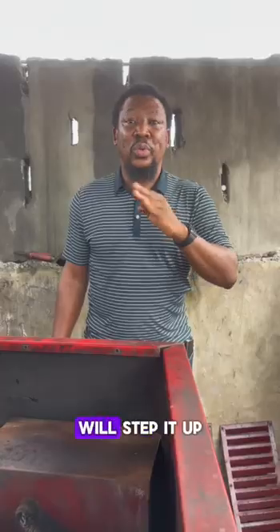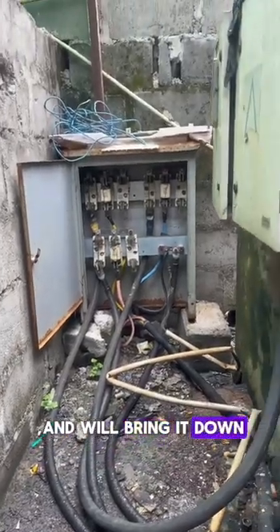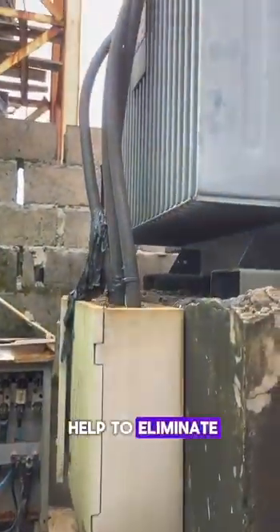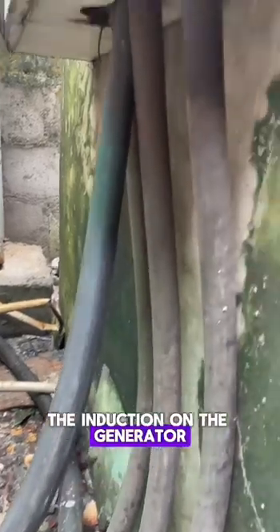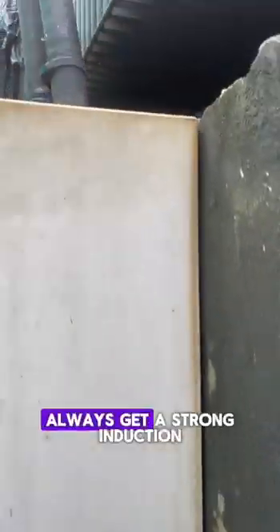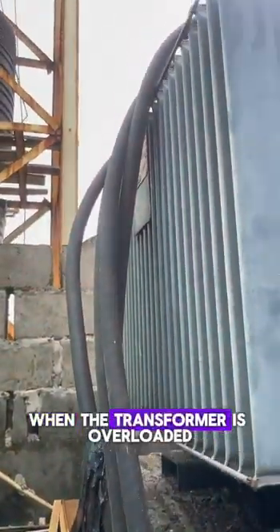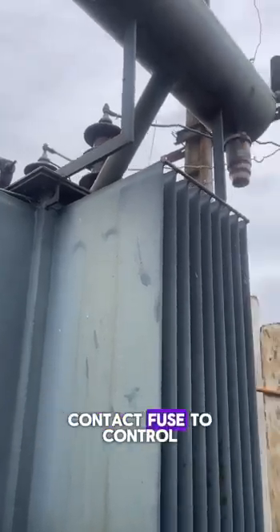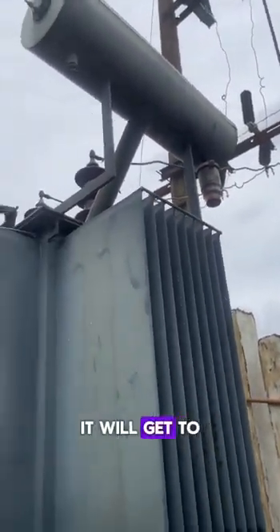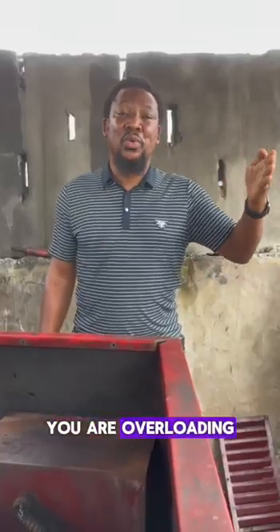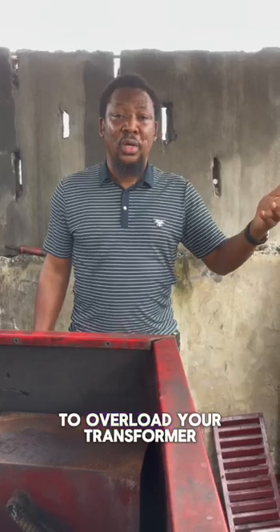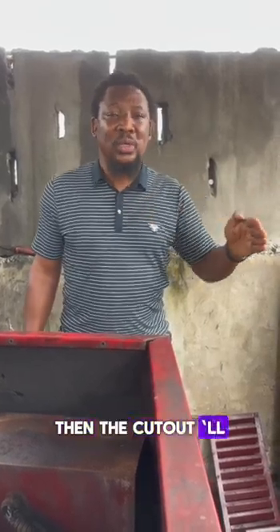So we step it up and bring it down to help eliminate induction on the generator. The generator will always get a strong induction when the transformer is overloaded, and we have a cutout fuse to control that. When you reach a certain state of overloading the transformer, the cutout will cut off.